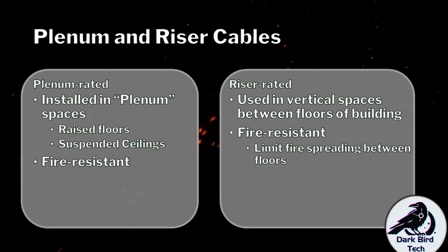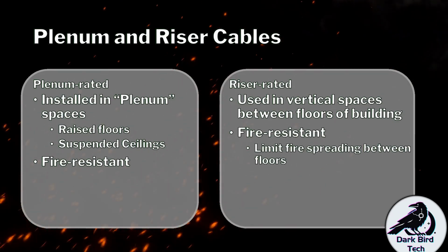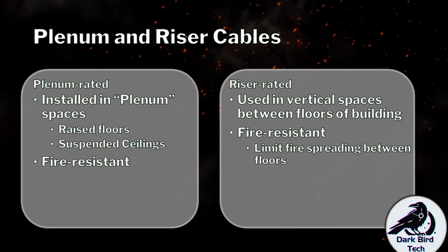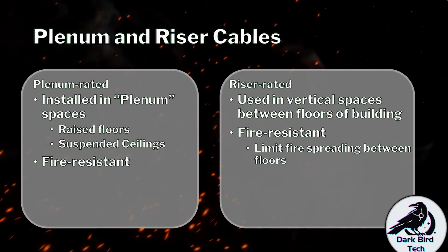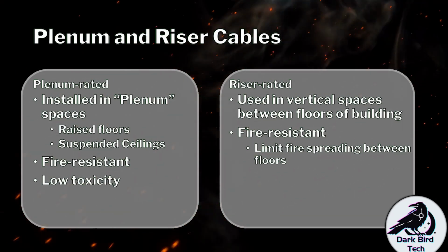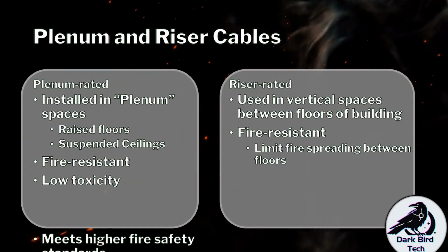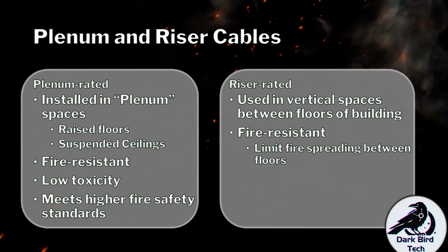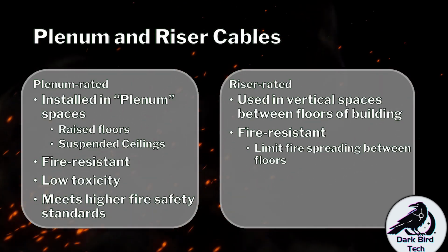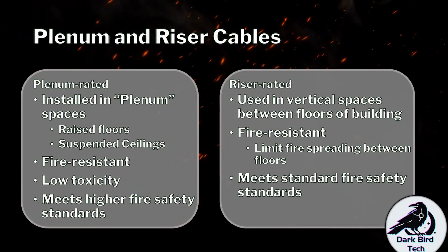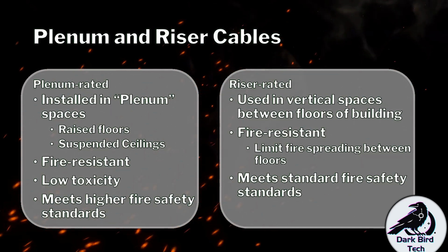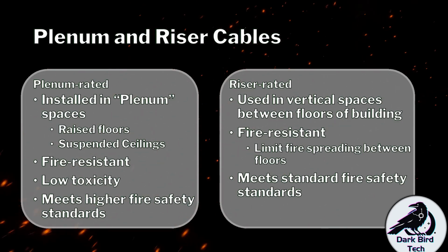They both offer us fire resistance with the intention of trying to stop the fire from spreading, and as you can imagine, in a multi-story building that would be very important to do. But also, the Plenum rated cables offer low toxicity and meet health and safety standards for fire safety. And the riser cables also meet fire safety standards. So it's an extra attribute you might want to pay attention to when doing structured cabling.